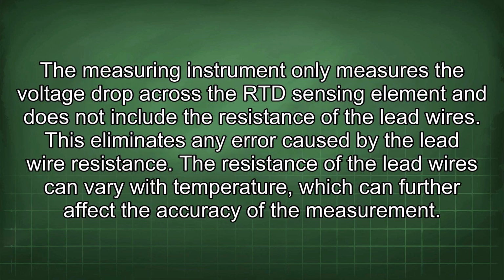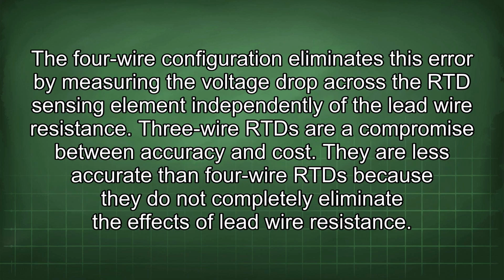The measuring instrument only measures the voltage drop across the RTD sensing element and does not include the resistance of the lead wires. This eliminates any error caused by the lead wire resistance. The resistance of the lead wires can vary with temperature, which can further affect the accuracy of the measurement. The 4-wire configuration eliminates this error by measuring the voltage drop across the RTD sensing element independently of the lead wire resistance. 3-wire RTD are a compromise between accuracy and cost.